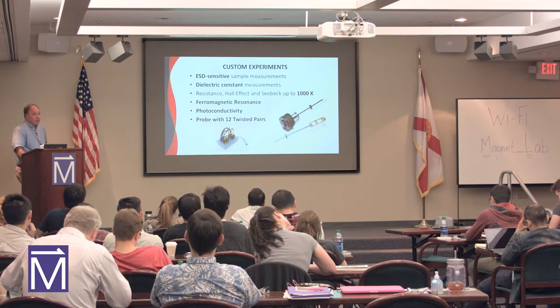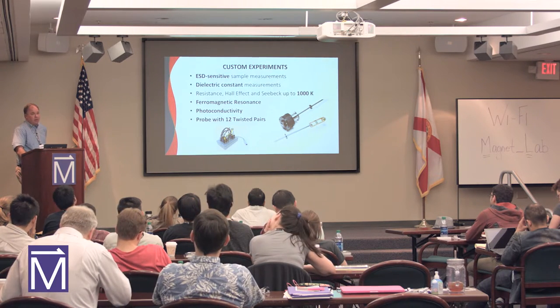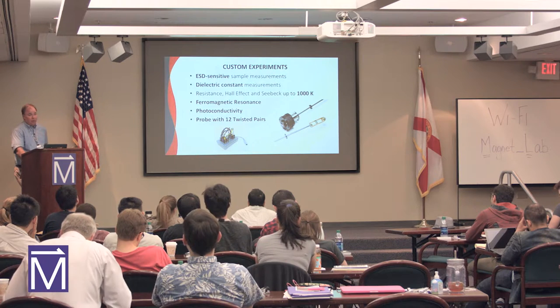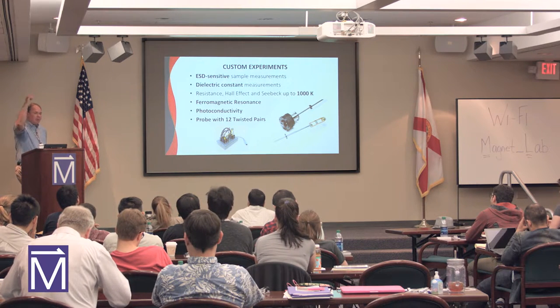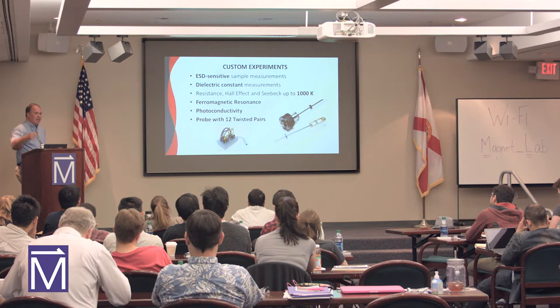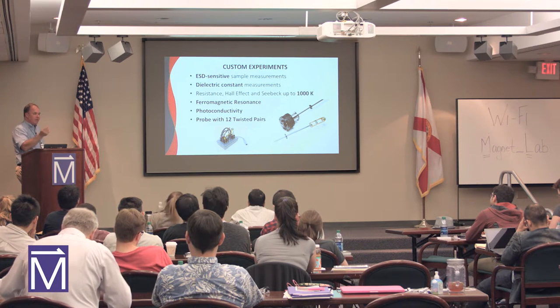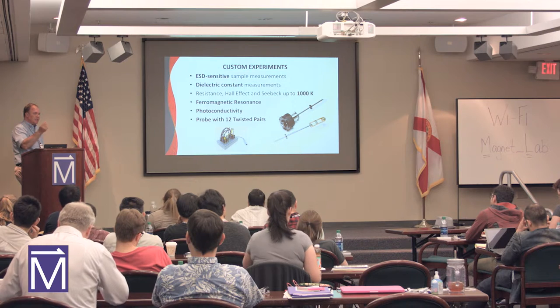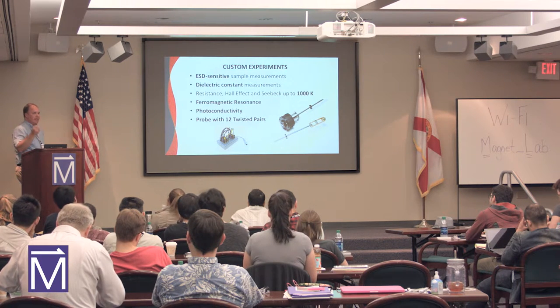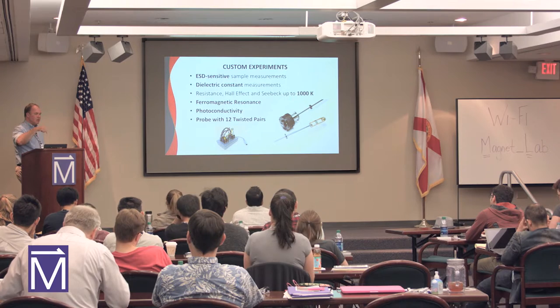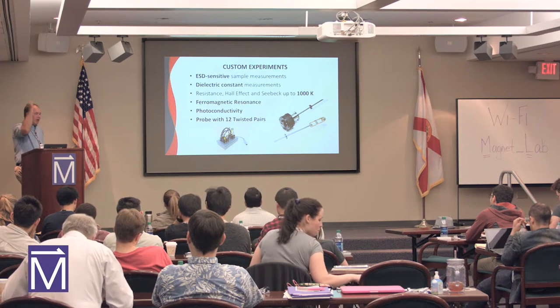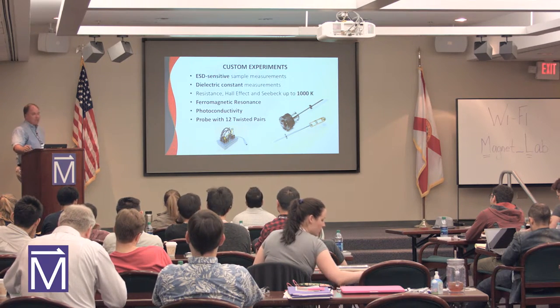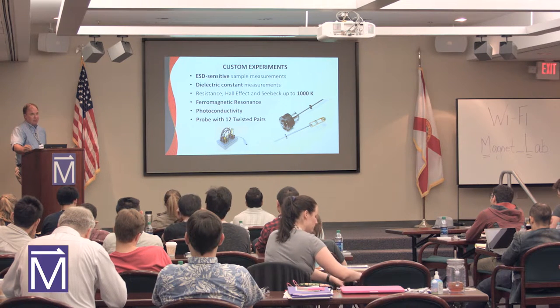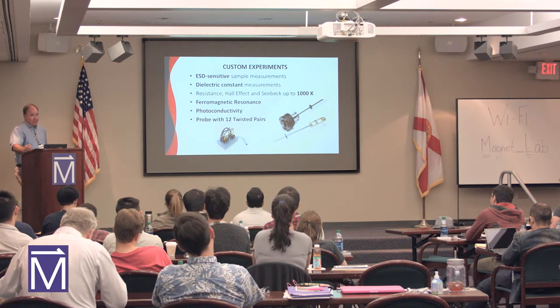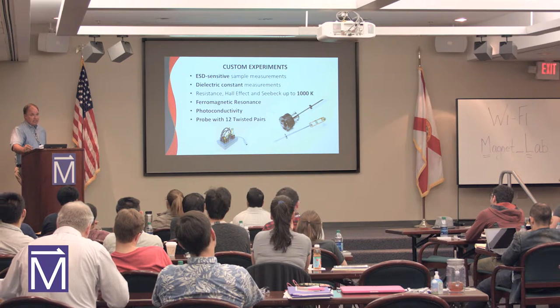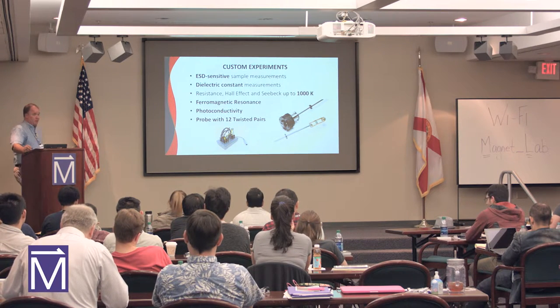But we essentially use what we call a multifunction probe. You can purchase a bare probe that you can wire up through the top of the sample space. So it still can plug into the bottom of the physical property measurement system connection, or you can eliminate that entirely. You can still use part of those wires to your sample, or you can run your own wires to your sample for these ESD graphene type samples. We wrote an application note that describes how you can use your own probe or our MFP probe to make these measurements.